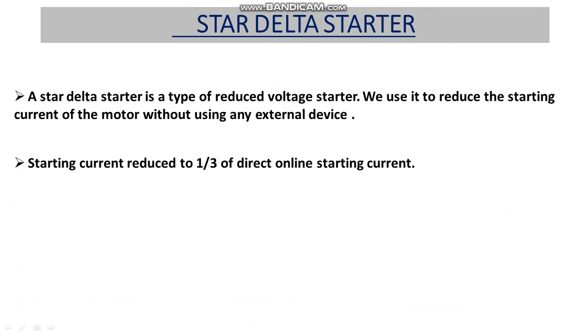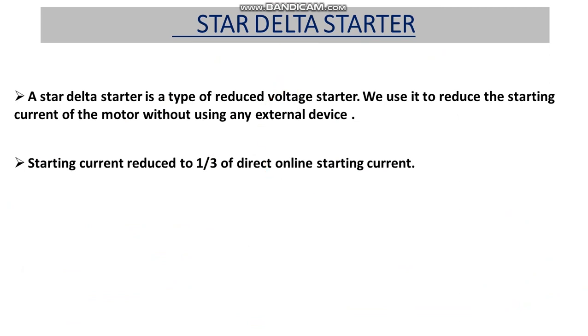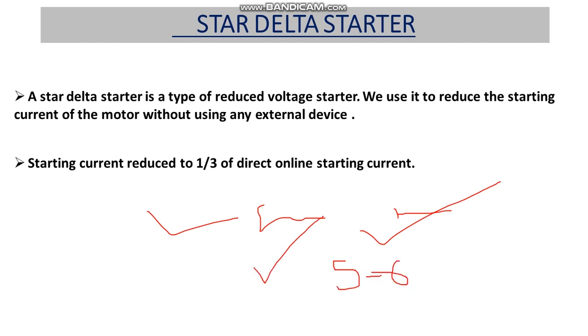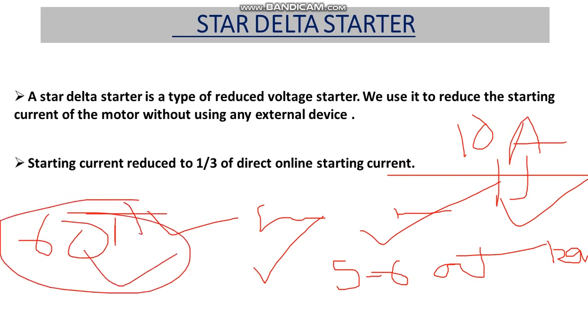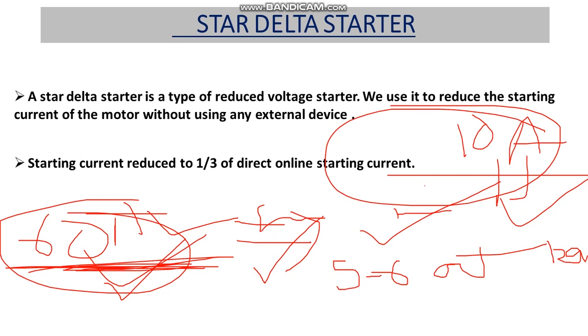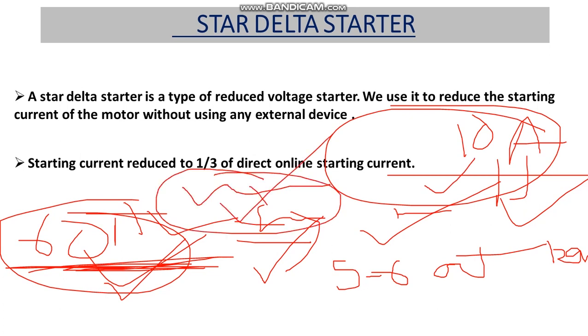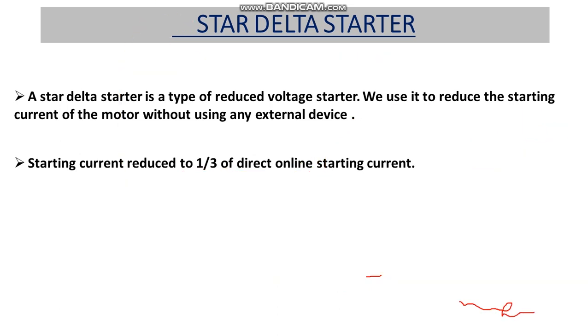The advantage of a star delta starter over a DOL starter is related to inrush current. When we start a three-phase induction motor, it draws five to six times the rated current initially. For example, if the motor is rated at 10 amperes, it will draw around 60 amperes at startup. This inrush current can burn the motor winding.